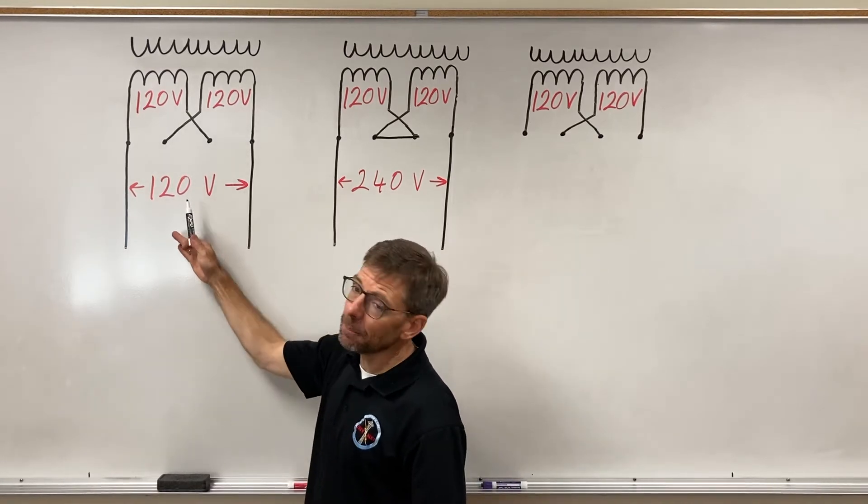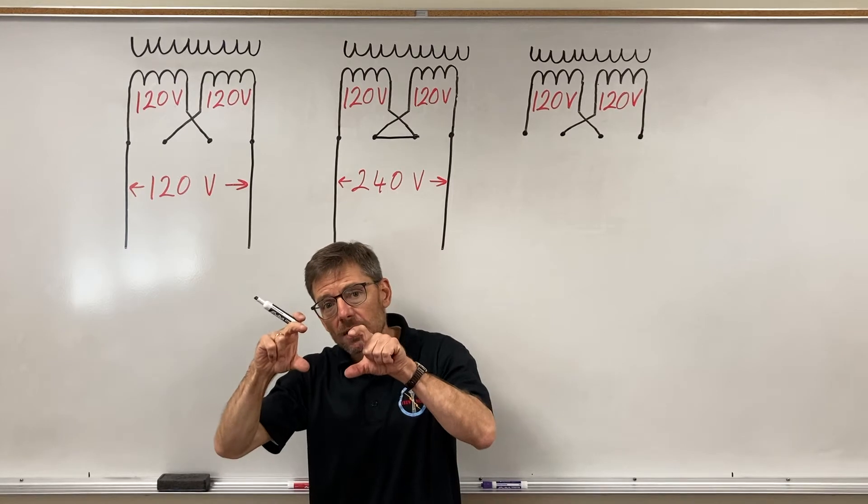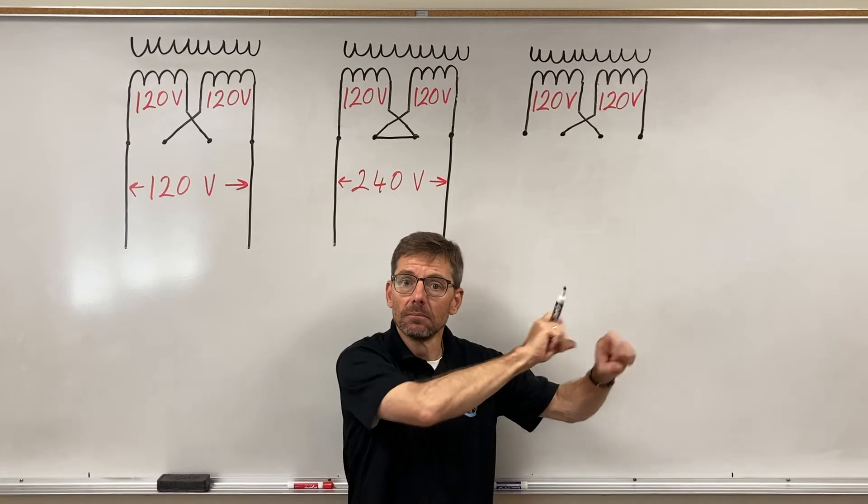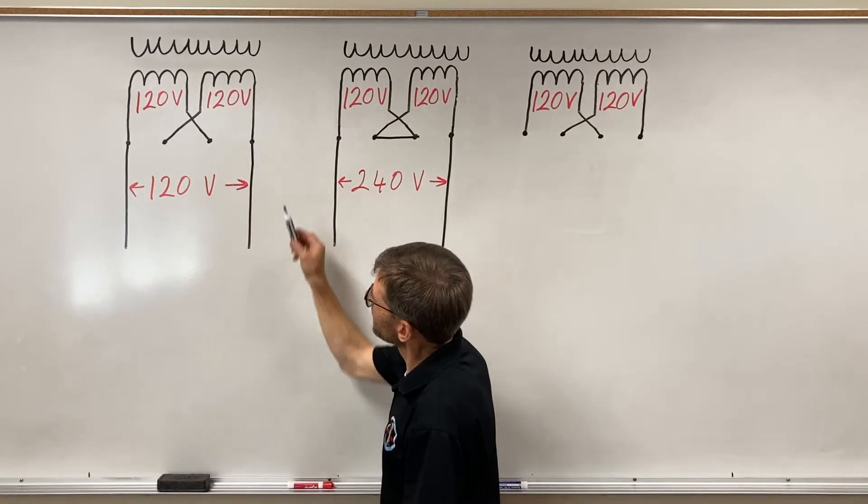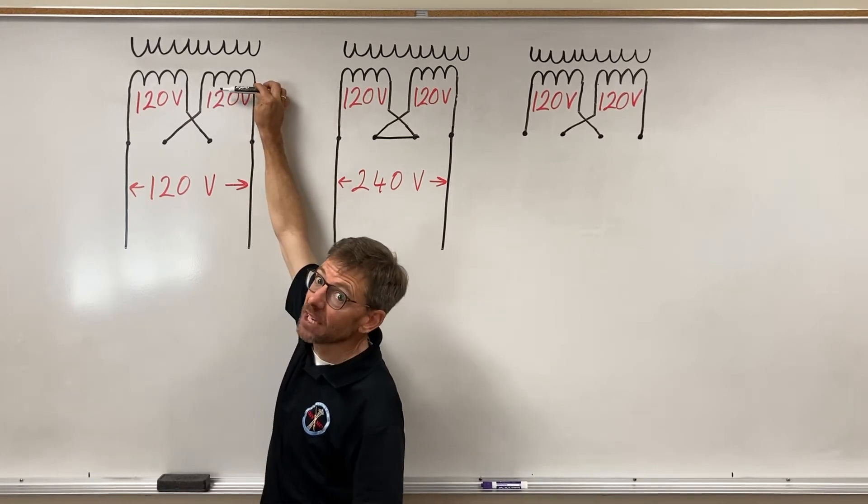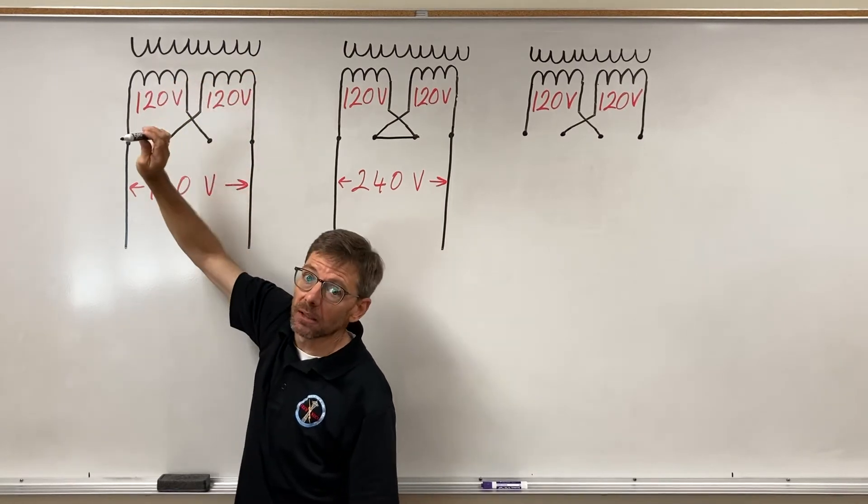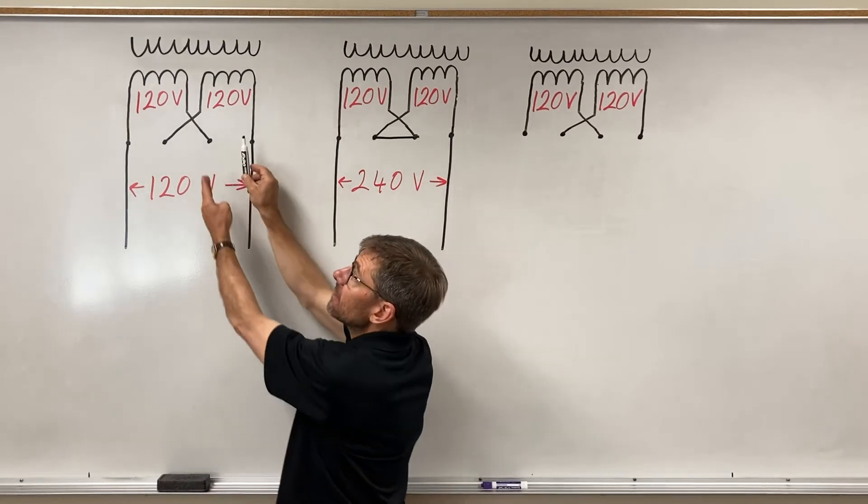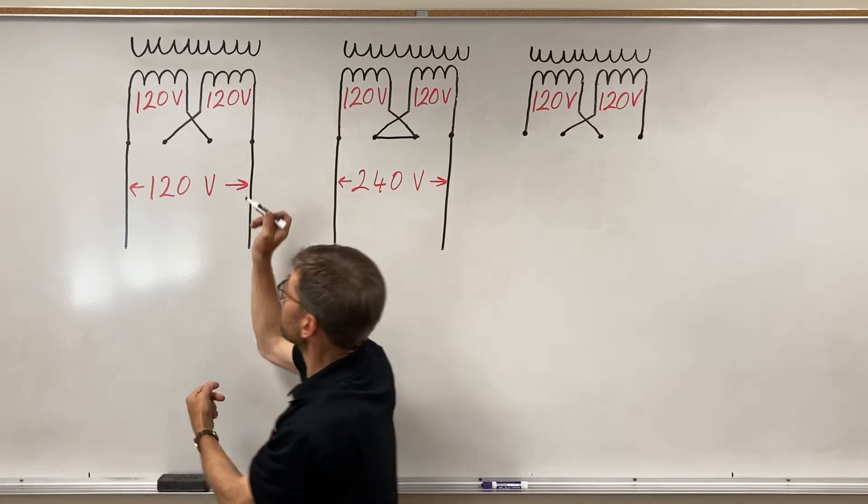But if I want to keep 120, just like those two batteries, I'm going to have to put them in parallel to keep the voltage the same. How do I do that? This winding and this winding each have induced in them 120 volts. So I want to take the, this is the key part here, I need to take the right side of each winding and connect them together.